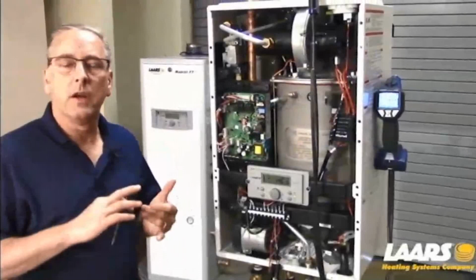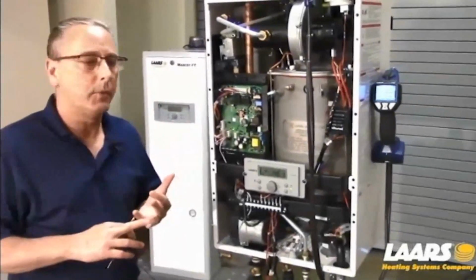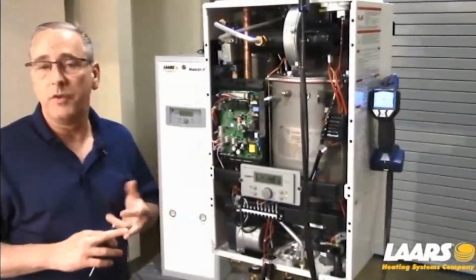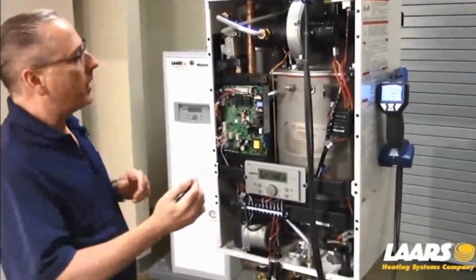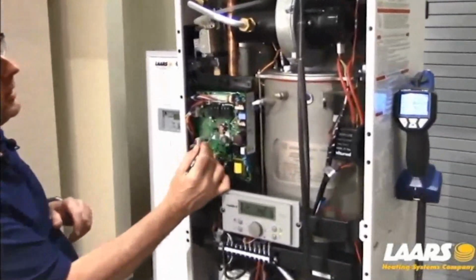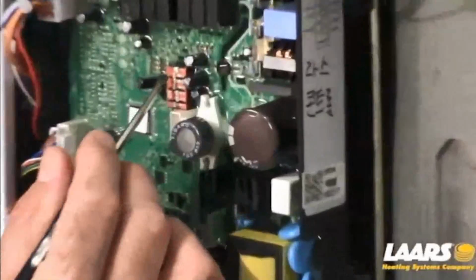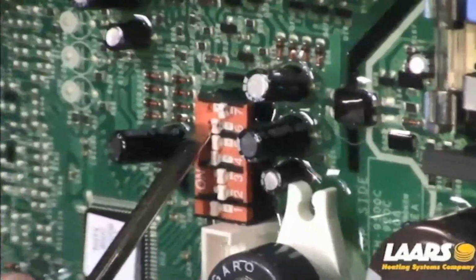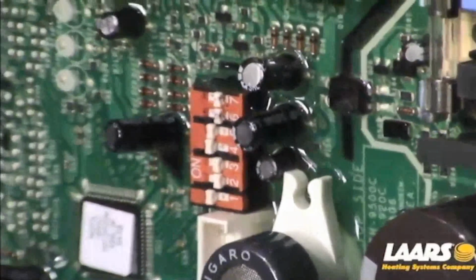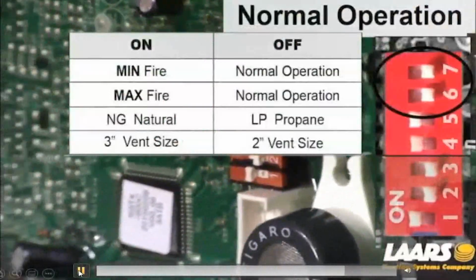So now that we've checked, again, our high fire CO2 is around 9.4%. Low fire was running around 9%. We want to make sure that we go back in and put this back into normal operation. In this case, dip switch 6, because we're in high fire, goes back to the right-hand position or the off position.